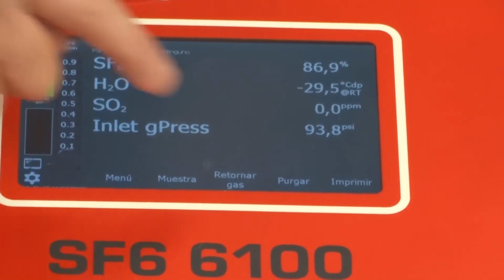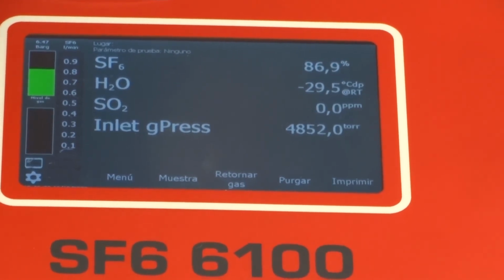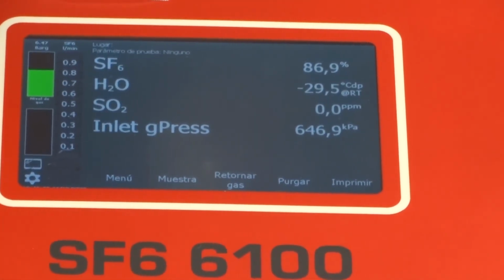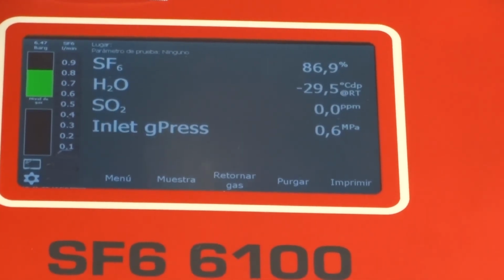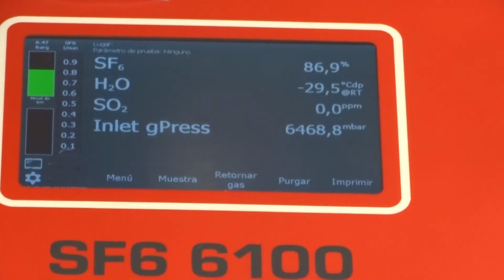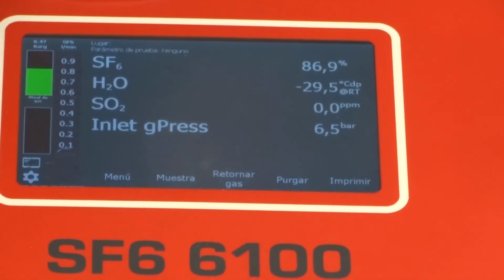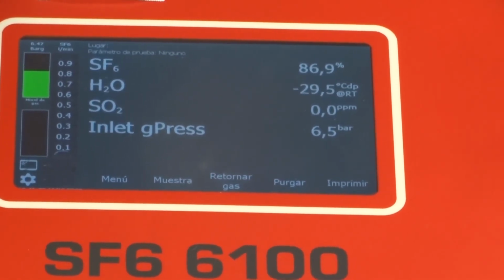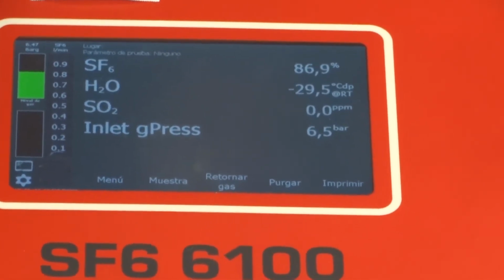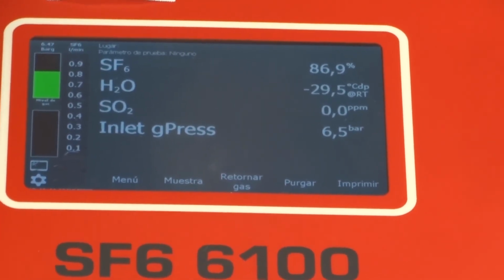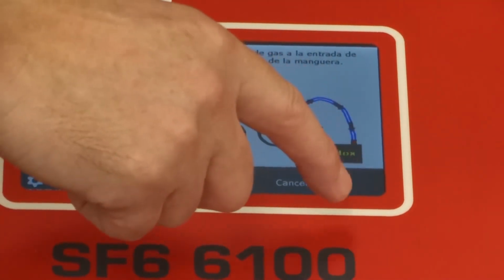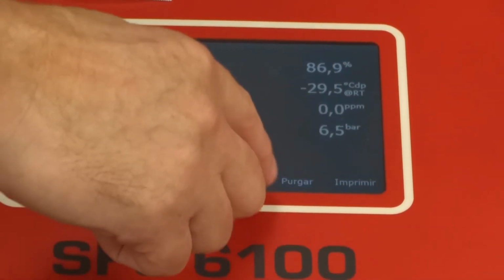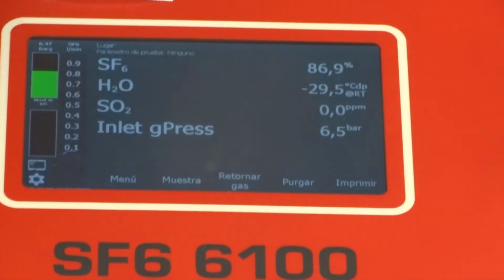Likewise, on the pressure reading, you can change the units to pounds per square inch, PSI, torr, kilopascals, megapascals, or millibar, or bar, which is currently reading 6.5 bar. And those are the main features of the gas analyzer. You can pump back at any time, and you can line purge at any time, and you can also print at any time.